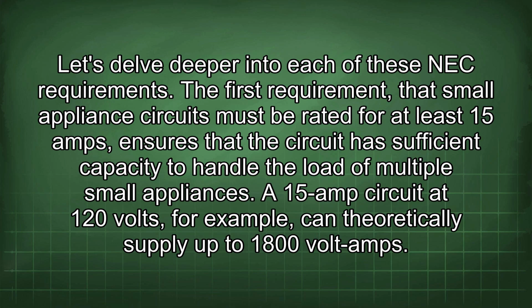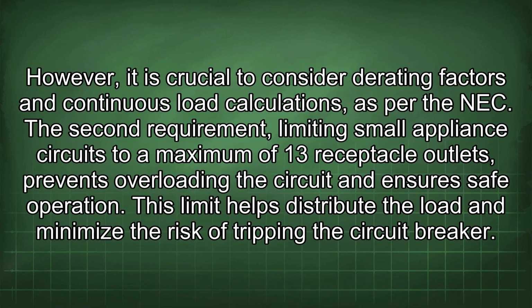The first requirement, that small appliance circuits must be rated for at least 15 amps, ensures that the circuit has sufficient capacity to handle the load of multiple small appliances. A 15 amp circuit at 120 volts, for example, can theoretically supply up to 1800 volt amps. However, it is crucial to consider derating factors and continuous load calculations as per the NEC.